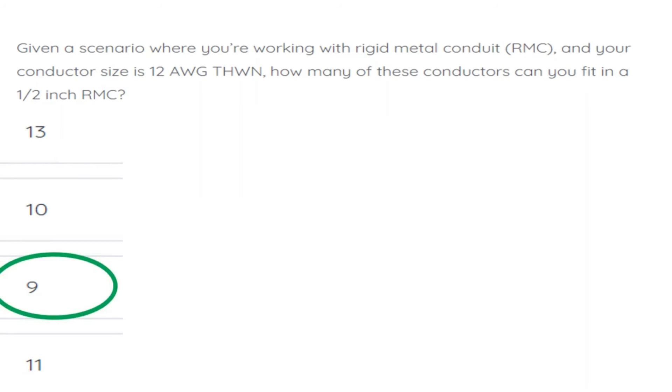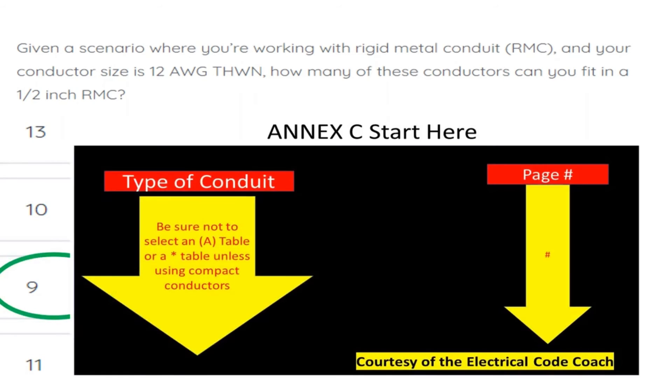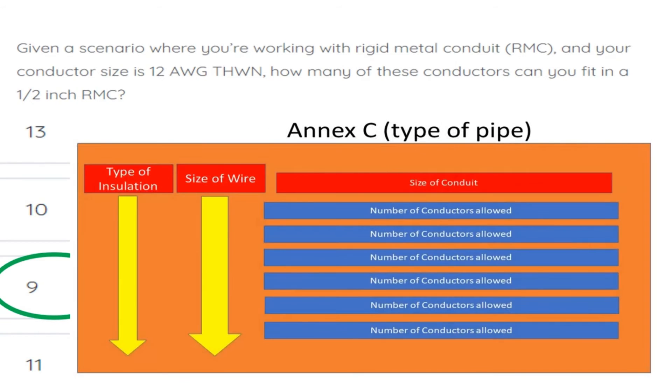For this problem, we're going to use Annex C. Start on the left-hand side to find your type of conduit, then cross over to the page number. When you get to that page, read the black bold heading of the table to make sure you're not in an A-designated table and that you're in the right type of conduit.